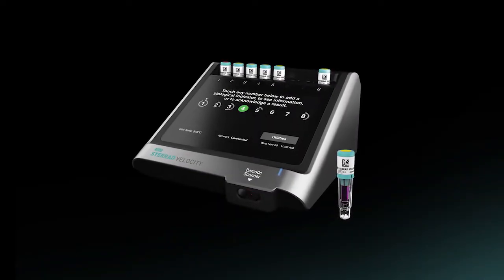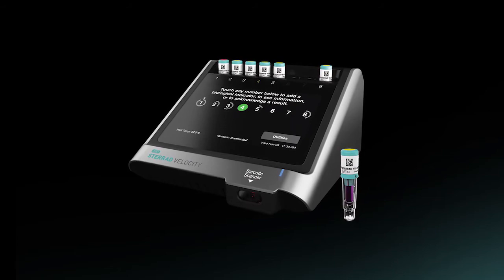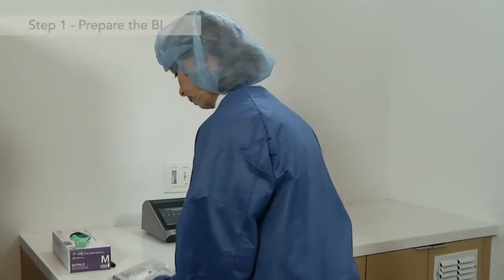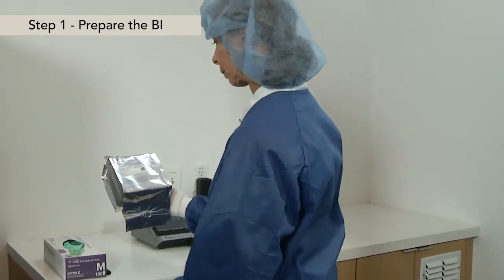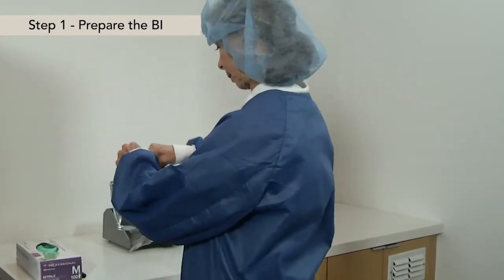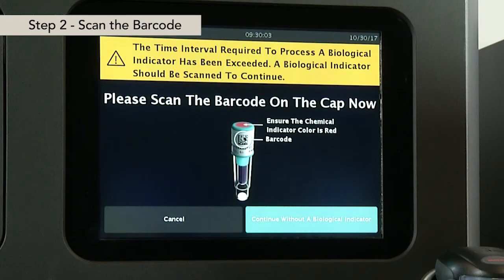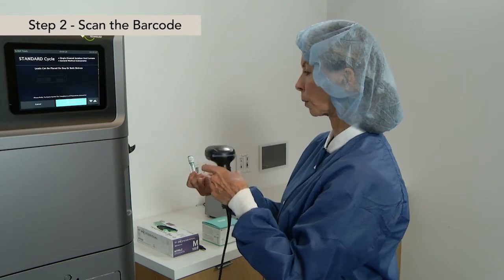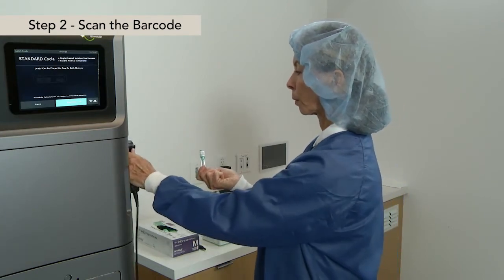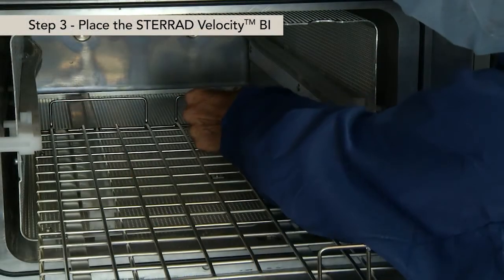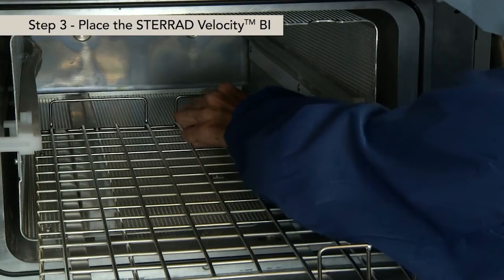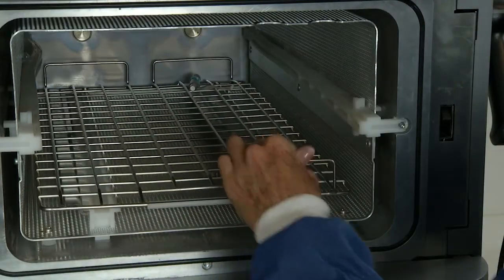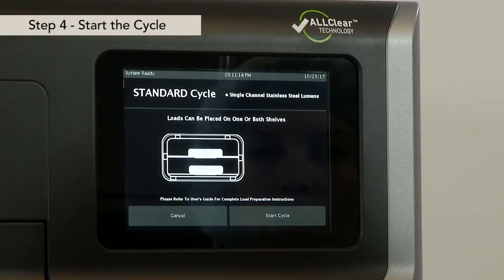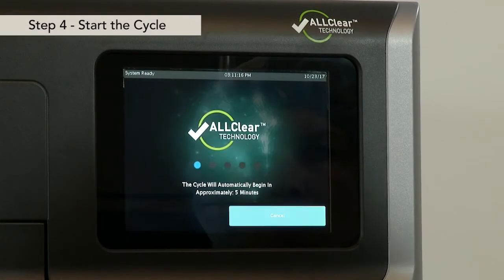If you are using the STERRAD Velocity Biological Indicator System, the following steps should be followed. Step 1. Prepare the BI as specified in the instructions for use. Step 2. After selecting the desired cycle, follow the on-screen instructions to scan the barcode with the sterilizer scanner. Step 3. Place the STERRAD Velocity BI as specified in the instructions for use. Step 4. Start the cycle and wait for the process to complete.